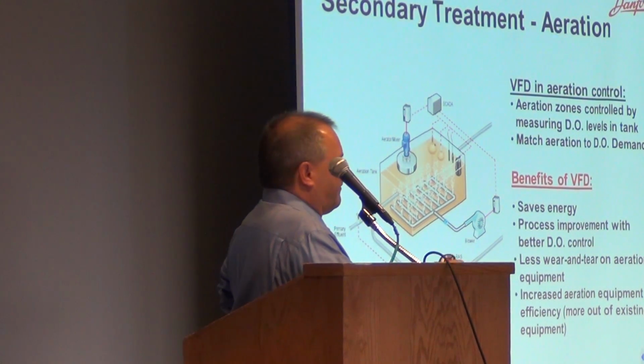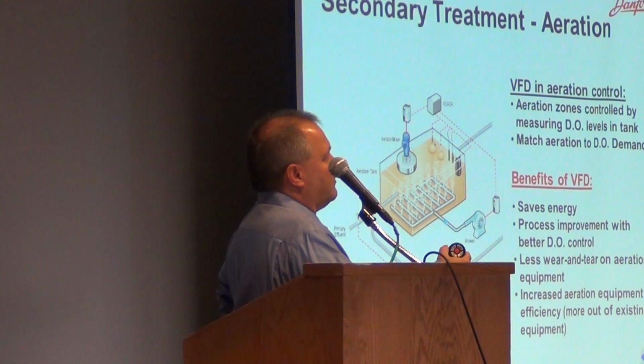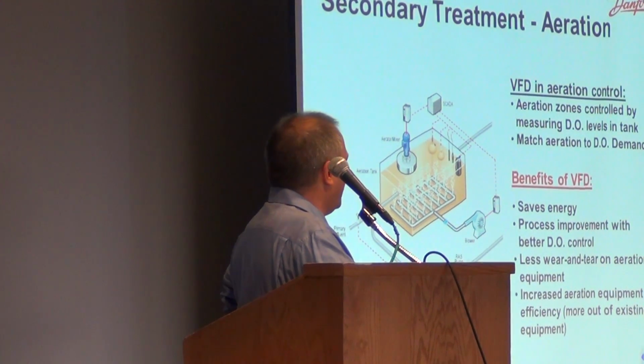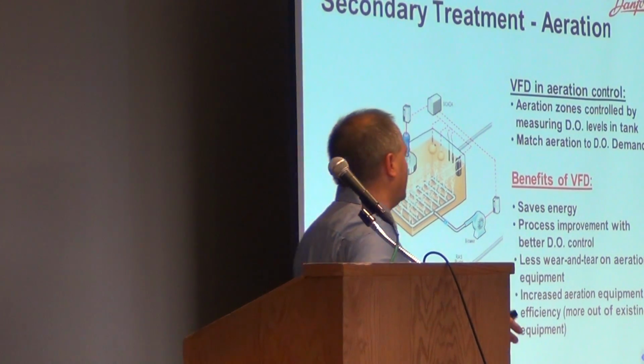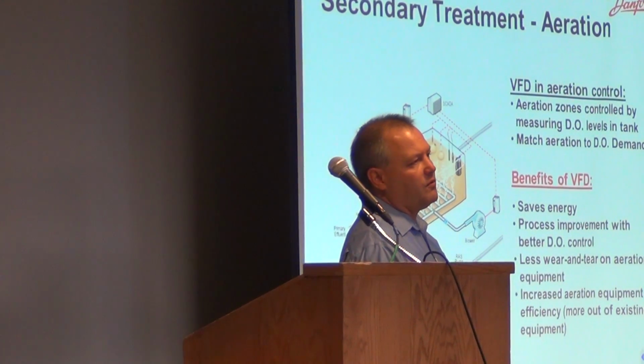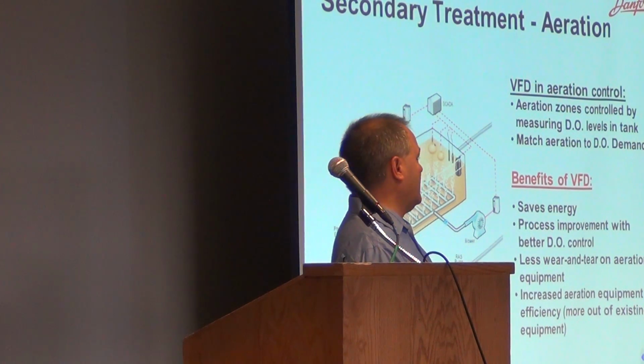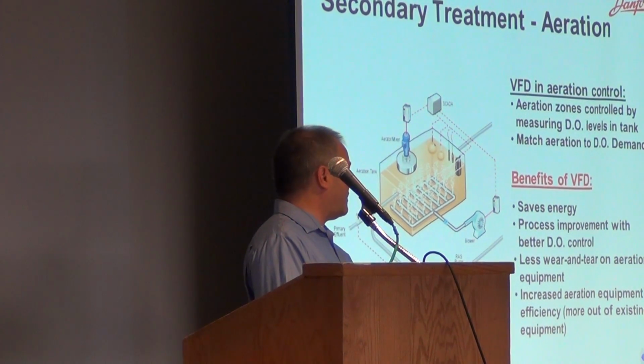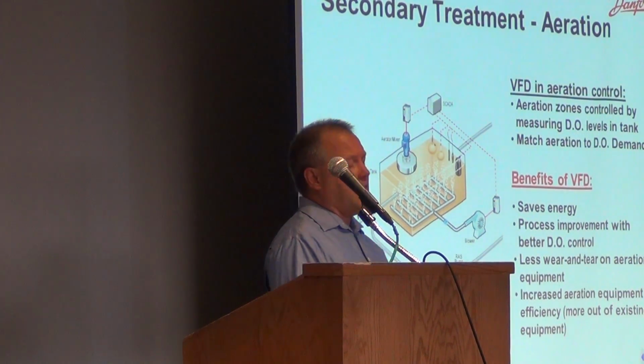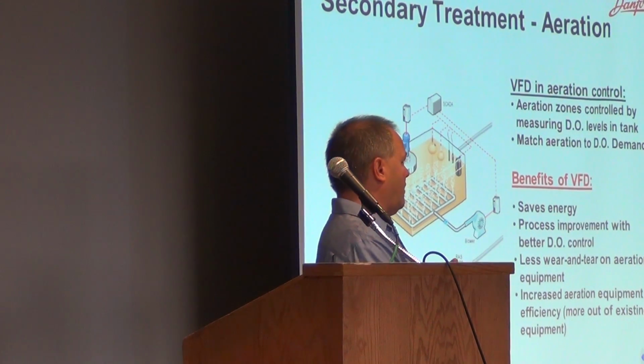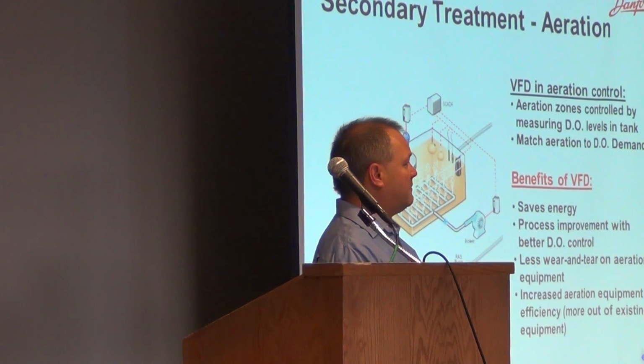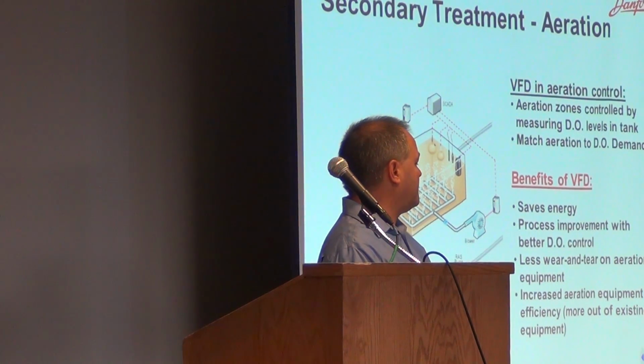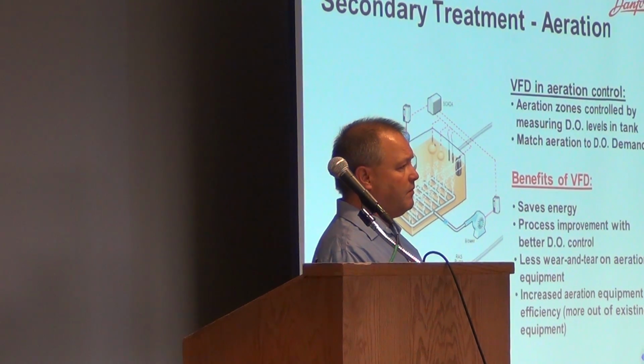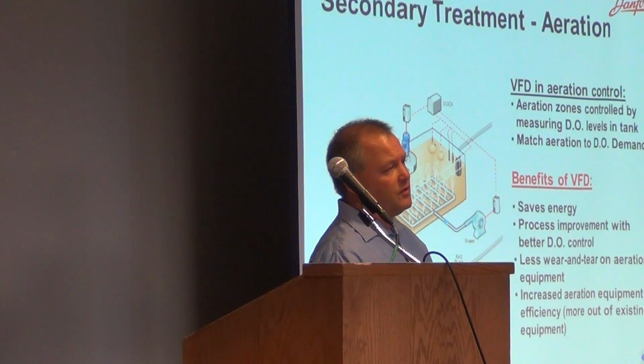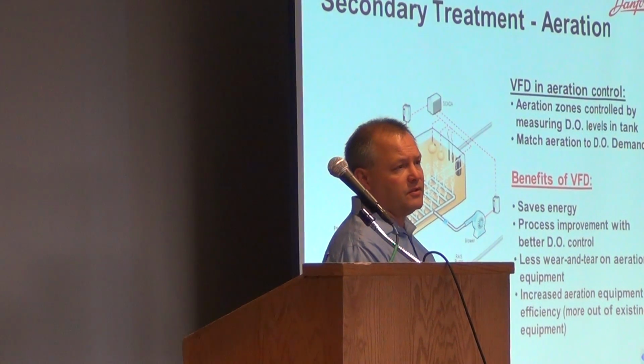If you need help figuring out the return on investment on a drive, or putting a drive on any part of your system, we're more than happy to work with you and your engineers to figure out what the return on investment on the drive would be. Currently, a lot of utilities are getting a rebate for putting drives on motors. They're also getting a rebate for changing the motor out, but for just the drive on the motor, most of the rebates right now give enough money that it pays for the drive. Basically, you're paying for the installation.